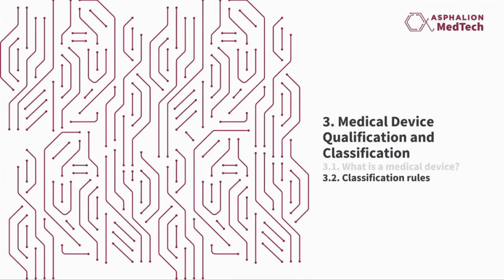Okay. So secondly, and once we know that our device is a medical device according to the definition given in Article 2 of MDR, the classification rules determine the risk level and regulatory requirements for the device. This classification influences the conformity assessment routes and the level of scrutiny by regulatory bodies. So understanding both the qualification criteria and classification rules is fundamental for ensuring that a medical device can be safely and effectively brought to the market. This knowledge forms the foundation for regulatory strategy and successful product development.